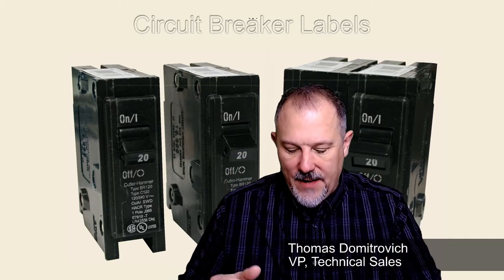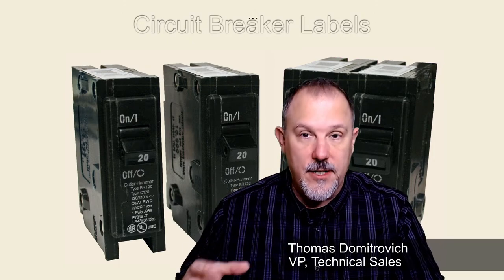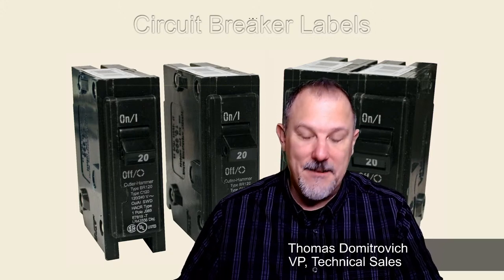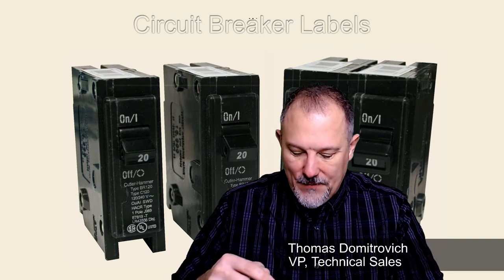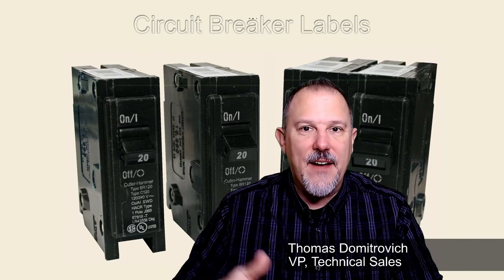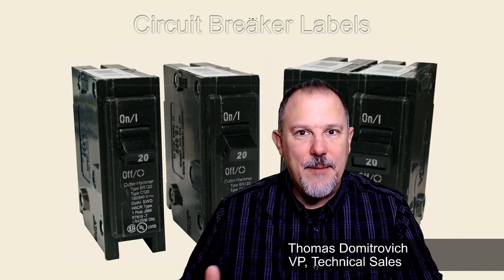If I put it this way, if I have 140 amps of current and I'm using the 75 degree column, I'm using a 1-aught, a larger conductor. If I'm using the 90 degree C, I'm using a number one. That's an easy way to look at this, right? Now, if I have a 145 amp load and I use the 75 degree C column, I have to bump the size up to a 1-aught. If I use the 90 degree C, I'm using a number one.